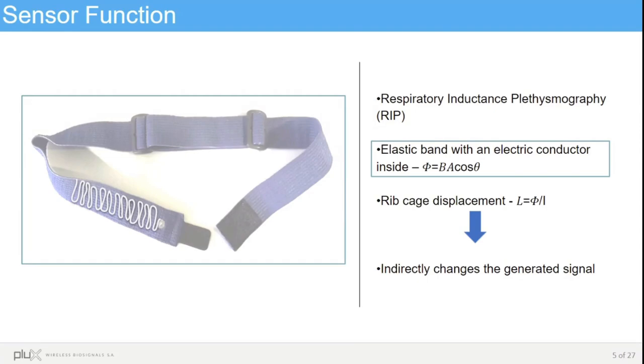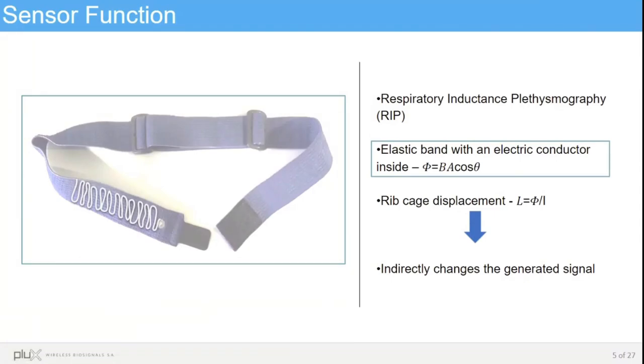A current passing through the coil generates a magnetic field around. The magnetic field combined with the cross-sectional area — the area of the core, which in this case is the chest — and the angle between the magnetic field vector and the cross-section generates the resulting magnetic flux, which is the expression you see inside the blue box. The magnetic flux generated by the current I determines the coil inductance L. The coil is then connected to an oscillator circuit that stores energy based on its frequency of oscillation, which is determined by the inductance of the coil.